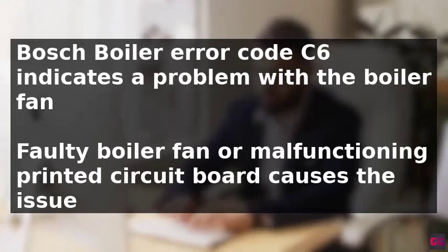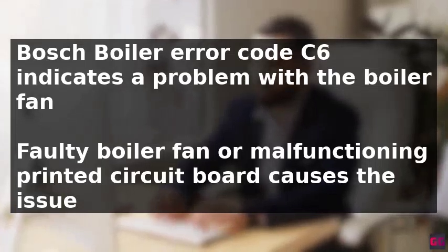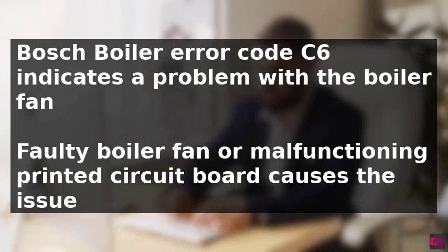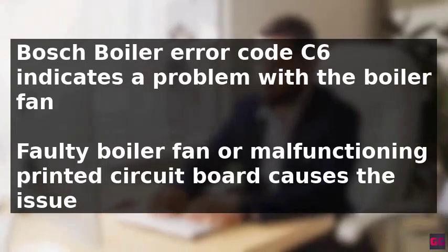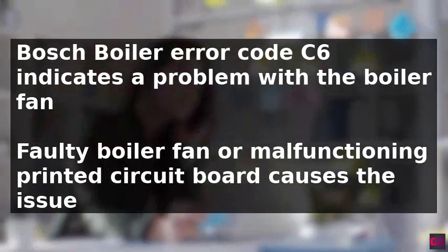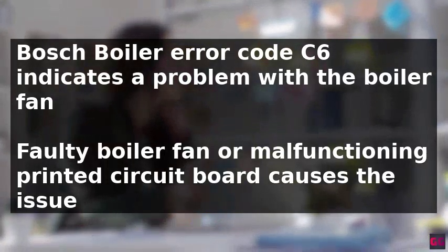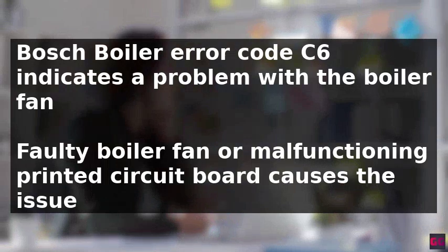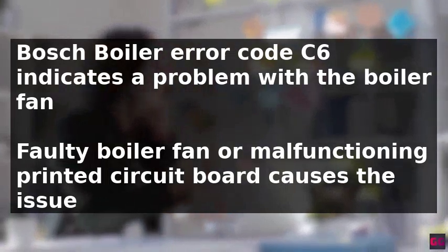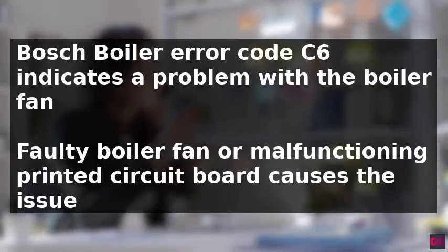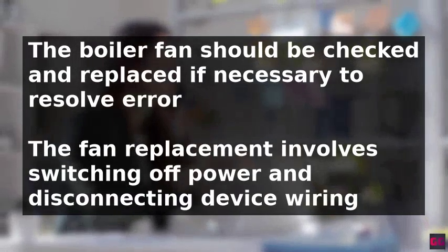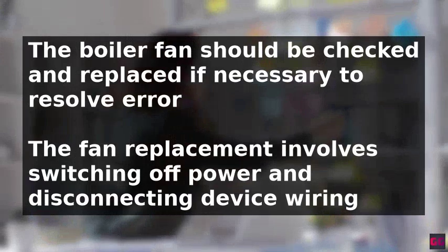The Bosch boiler error code C6 indicates a problem related to the boiler fan. This issue can be caused by a faulty boiler fan or a malfunctioning printed circuit board (PCB).